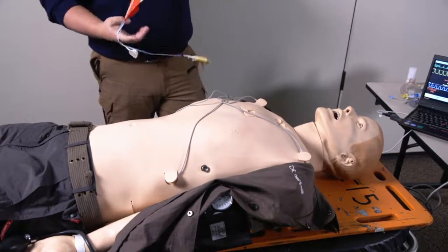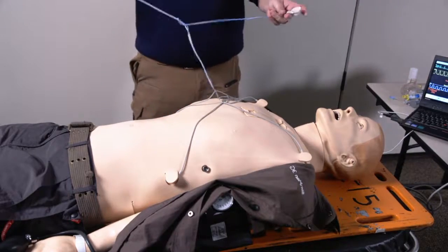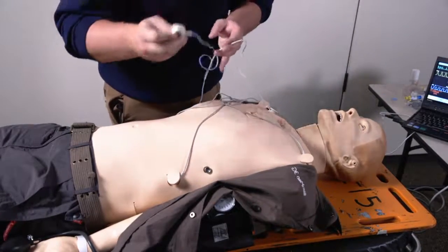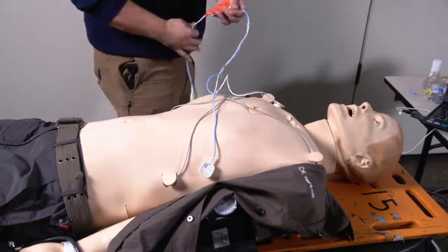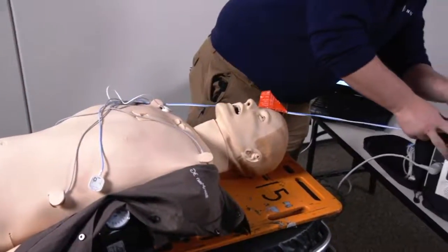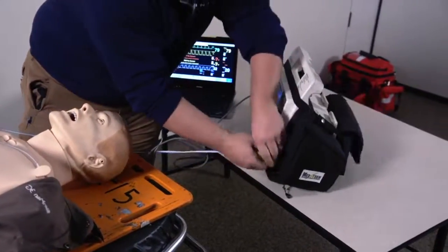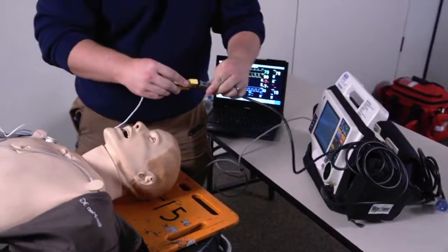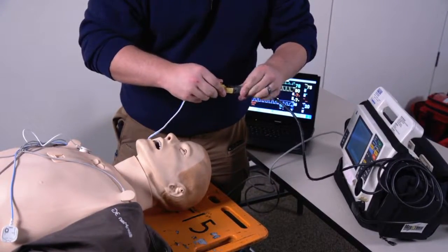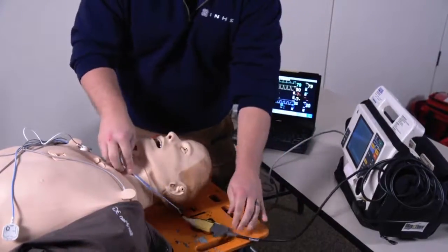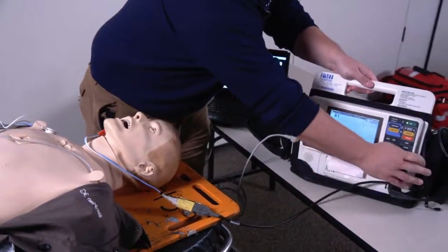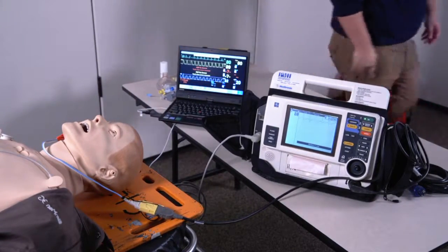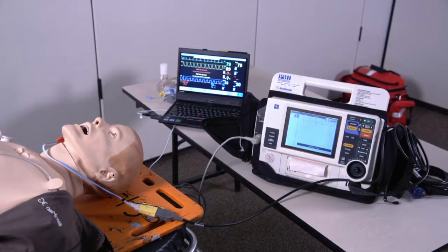We'll have to use the specific cables that will attach to him and then hook up to your LifePak. Just like the patches, each of the cable leads shows exactly where to place them on Sim Man. And just as you would hook up to the patches, you hook up to the cables instead.